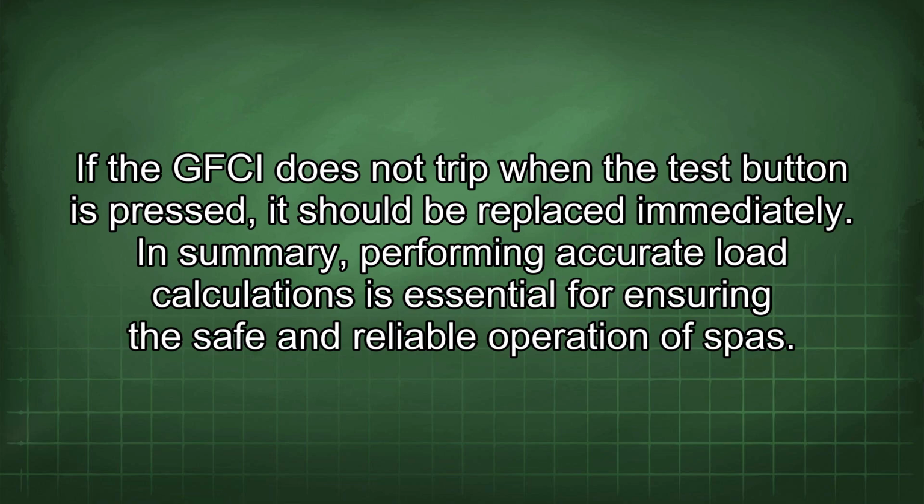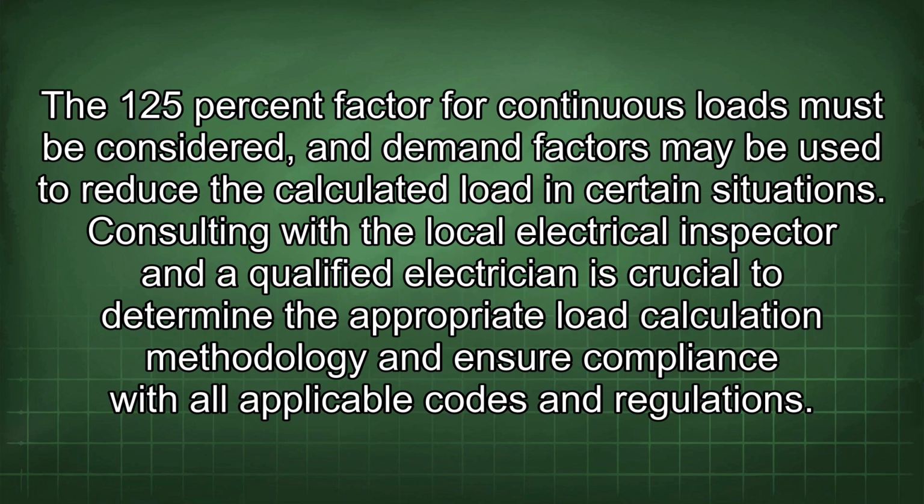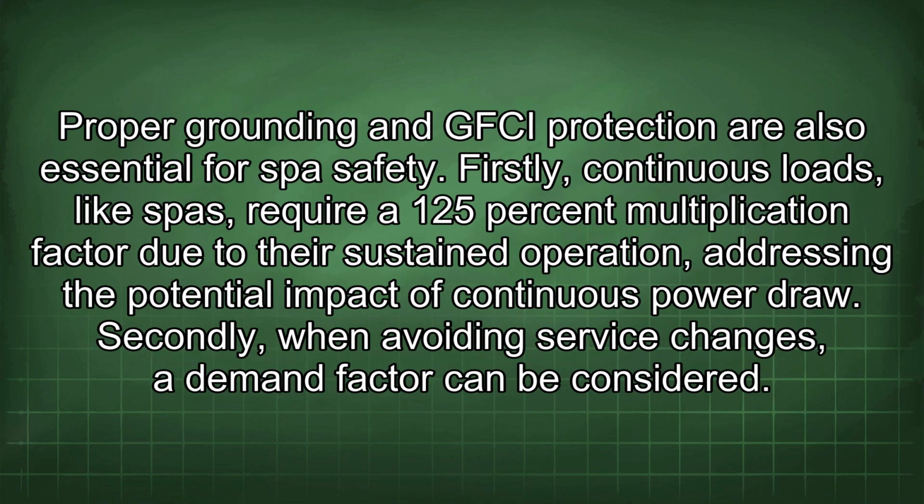In summary, performing accurate load calculations is essential for ensuring the safe and reliable operation of SPAs. The 125% factor for continuous loads must be considered, and demand factors may be used to reduce the calculated load in certain situations. Consulting with the local electrical inspector and a qualified electrician is crucial to determine the appropriate load calculation methodology and ensure compliance with all applicable codes and regulations. Proper grounding and GFCI protection are also essential for SPA safety.